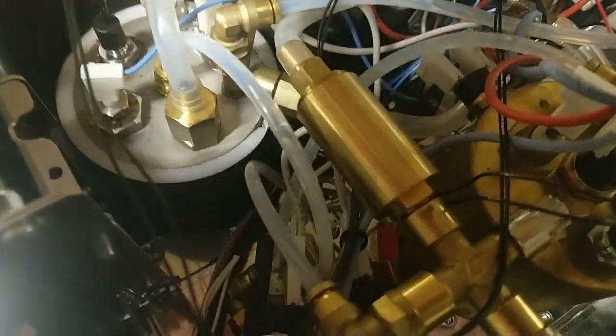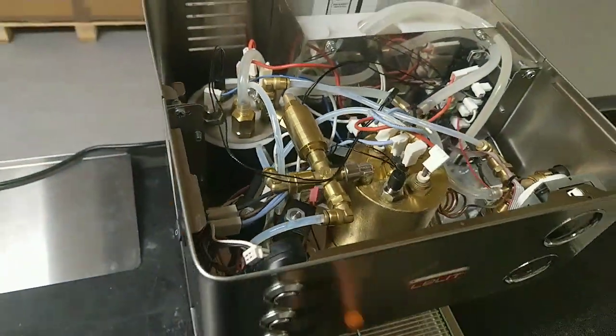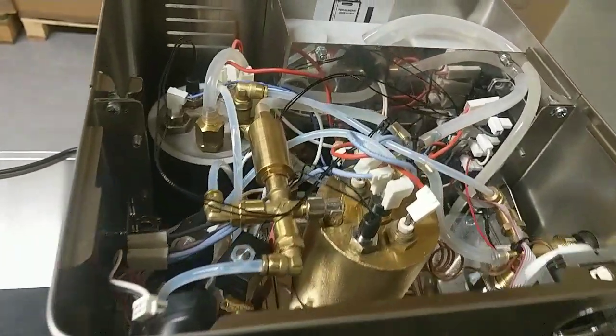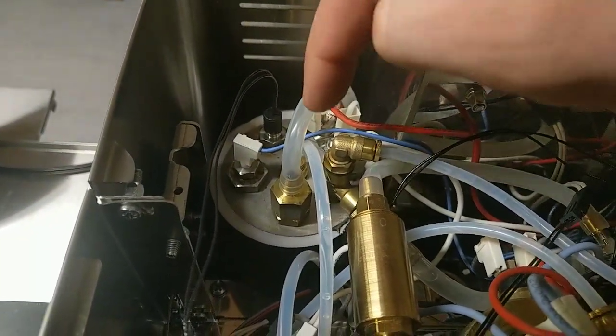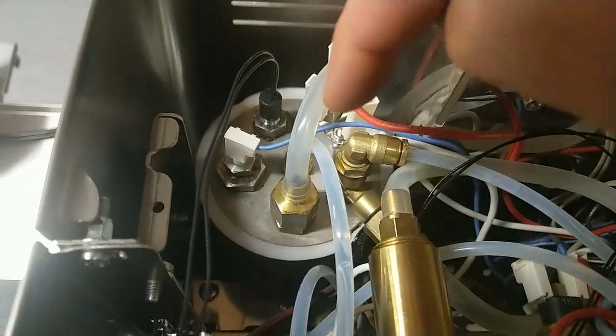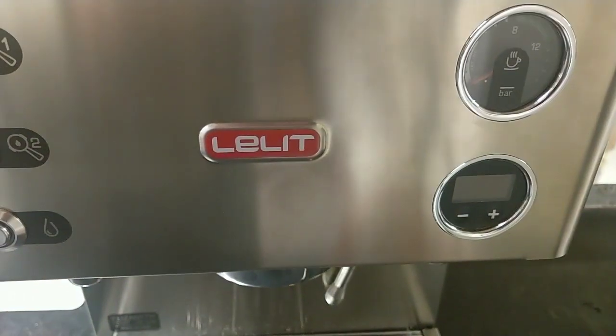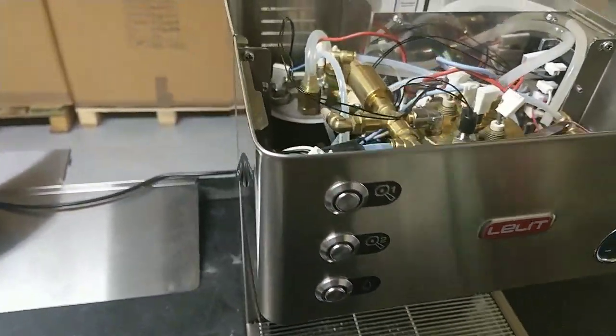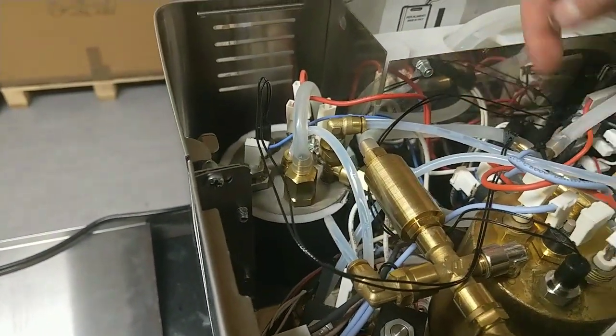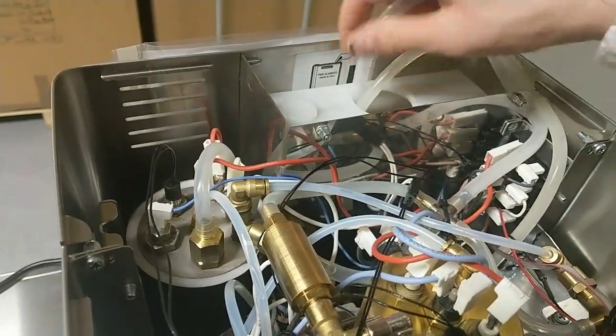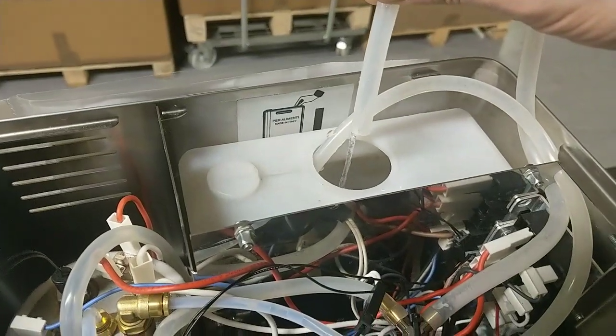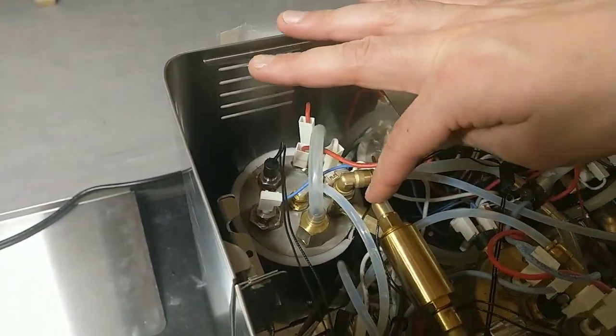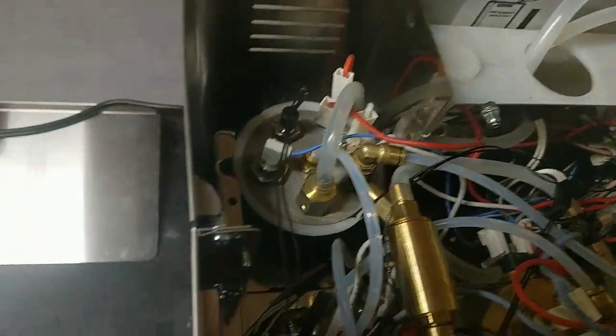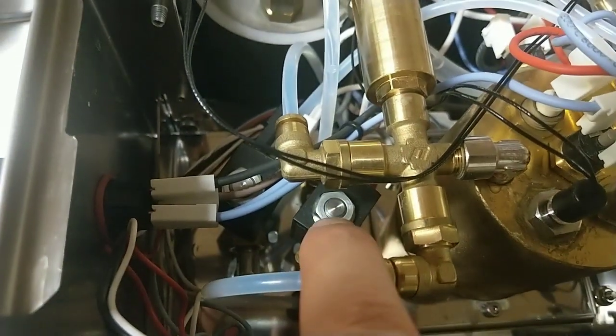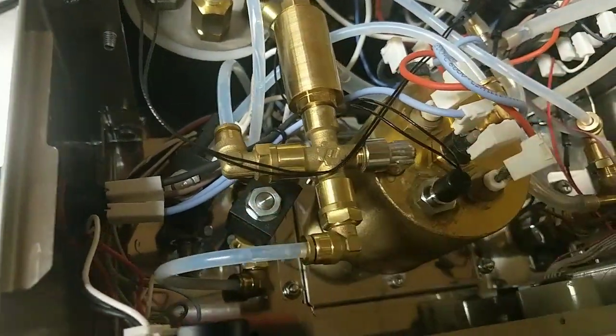I've disconnected the wire from the solenoid valve, the red wire, because I have to simulate what happens if I have a problem on this during the filling up of the steam boiler. What happened is that the pump continues running, and the water came out from here, and from here, and from this valve, because in this case this solenoid valve is not open.